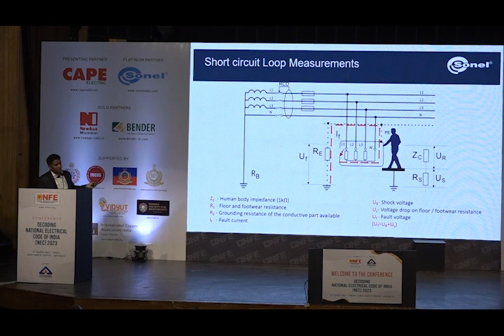Then comes the next protective device, which is your RCD device. Before I get into the testing, I wanted to briefly show you - I've been following the CEA website as the regulation was being made. The first time they said: limit earth resistance sufficiently low. This was a previous standard, just copy-pasted. So they said, limit earth resistance sufficiently low. Now the new statement says: limit earth fault loop impedance shall be maintained sufficiently low. Which means what?